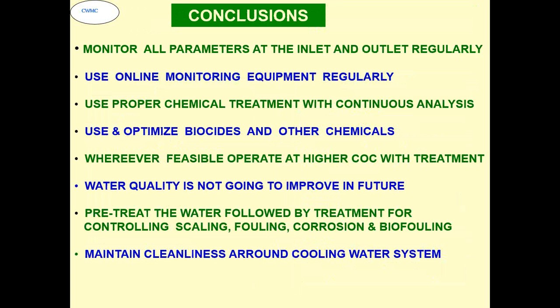As a conclusion: monitor all parameters at the inlet and outlet regularly, use online monitoring equipment regularly, use proper chemical treatment with continuous analysis, and use and optimize biocides and other chemicals. Wherever feasible, operate at higher COC with treatment. Water quality is not going to improve in future, which we have to keep in mind. Pre-treat the water, followed by treatment for controlling scaling, fouling, corrosion and biofouling. Maintain cleanliness around the cooling water system.